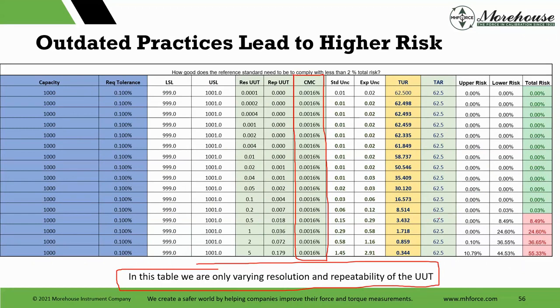So TAR, again, 62.5 the whole way through. TUR went from 62.5 down to 0.344. And if we look at this table, you can start seeing total risk, where it is. Right here, we start getting some risk based on the capacity and the measurement location and everything else. So it's a table. It allows you to do a lot of different things.